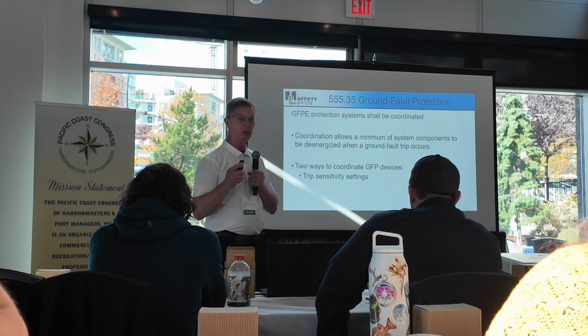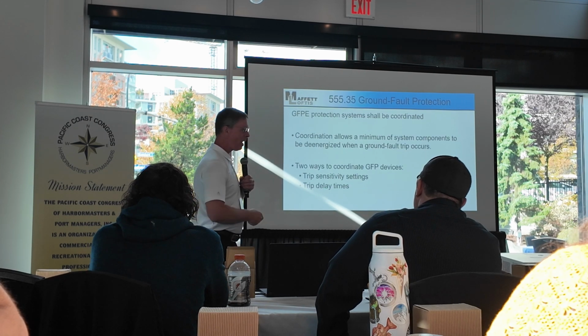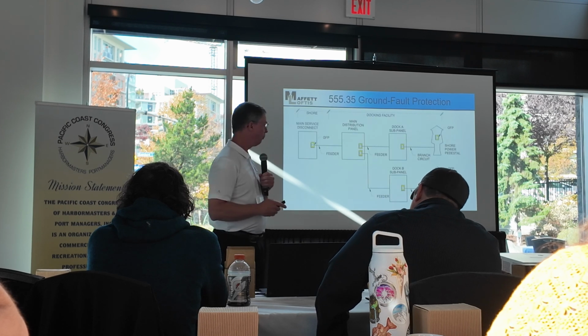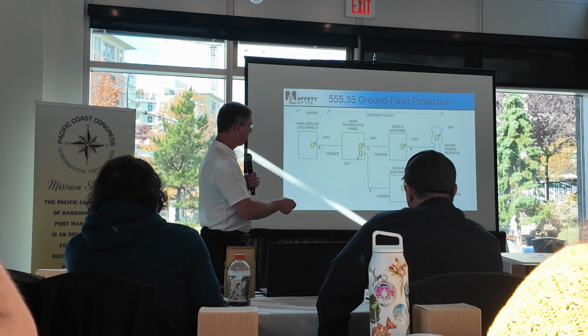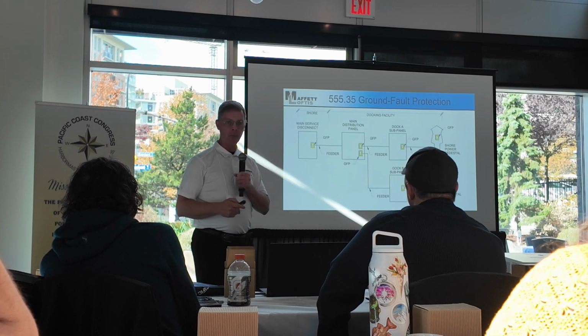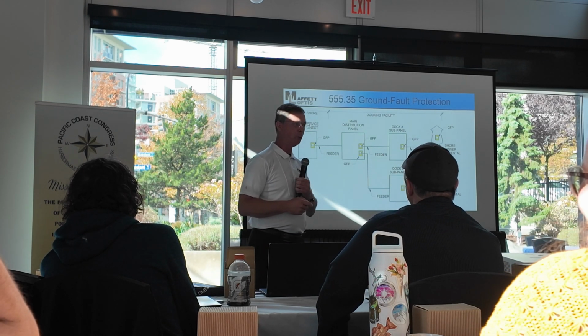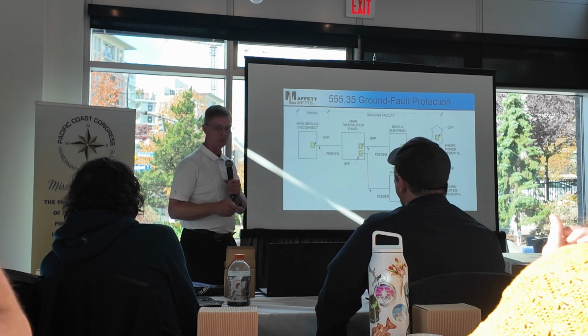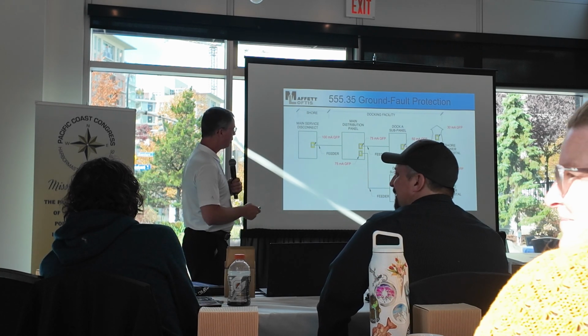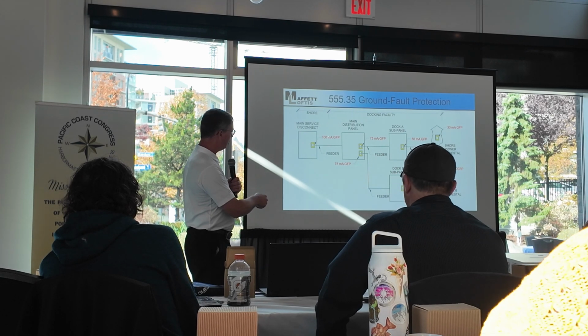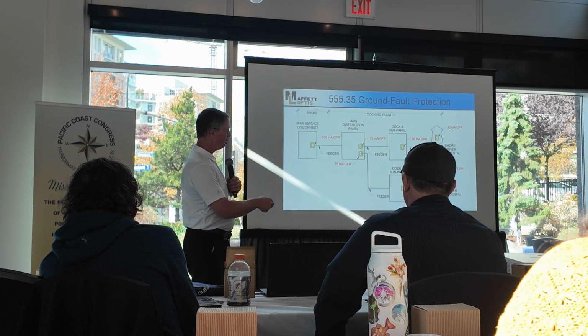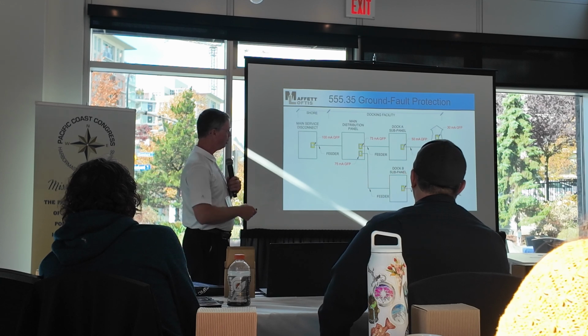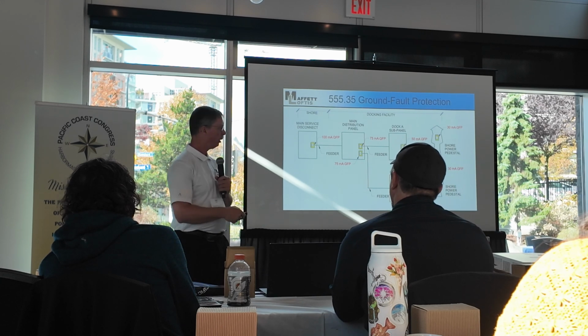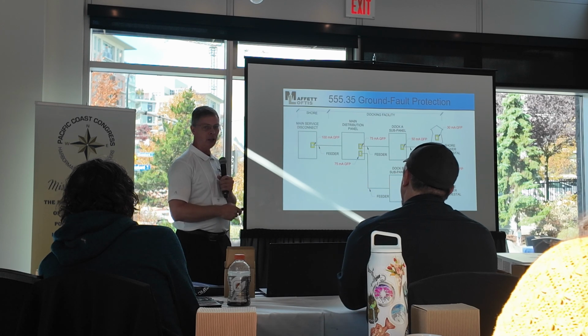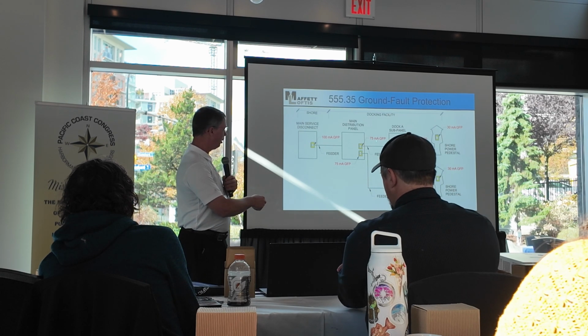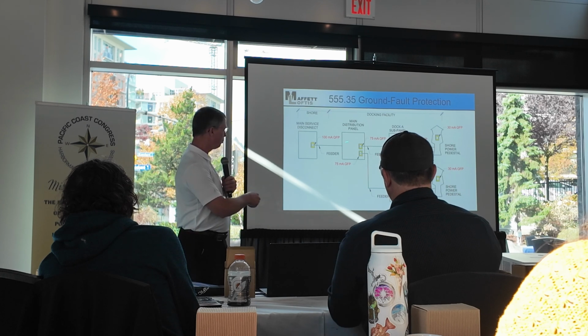The other is through timing. Okay? How fast are those going to trip? Let me give you an example. Say that we put GFPE throughout the entire marina. Because you've got plenty of money, you need to spend it somewhere, so we're going to put GFPE throughout the entire marina. Just go with me on that one. So you've got 30 milliamps here, 50 there, 75 here, and 100 there. So a boat that comes in that pulls 40 milliamps, it's only going to trip there. But if a boat comes in and it pulls 60 milliamps of leakage current, it could trip there or here. If it pulls 80 milliamps, it could trip there, or here. Or if it's about 400 milliamps, it could trip up here and trip out the entire marina.